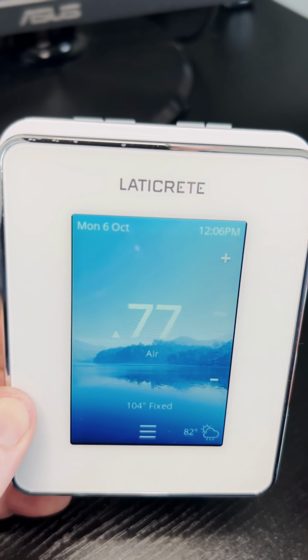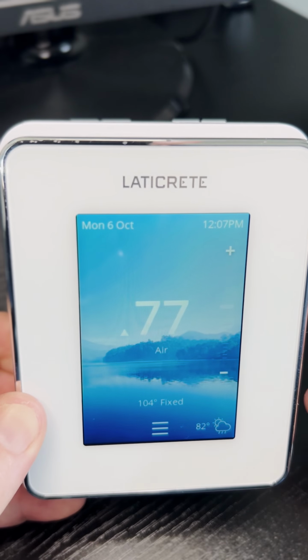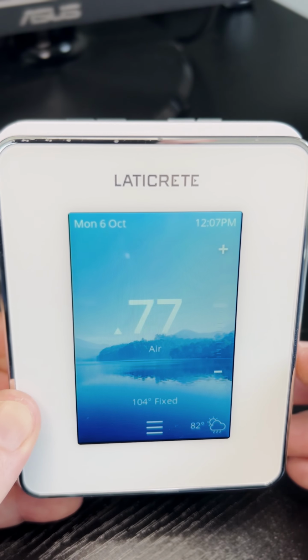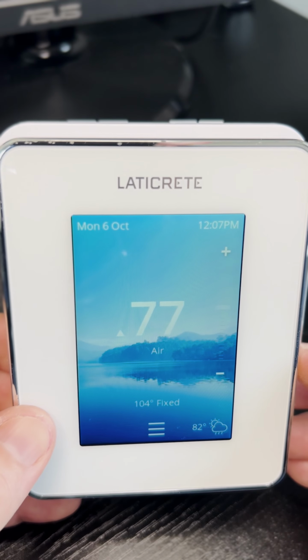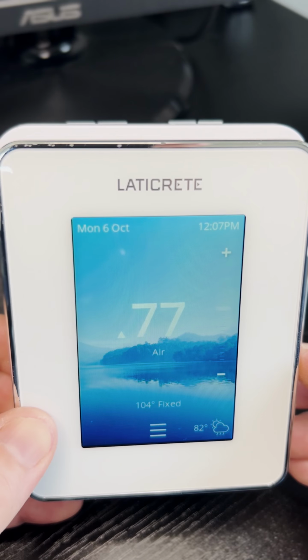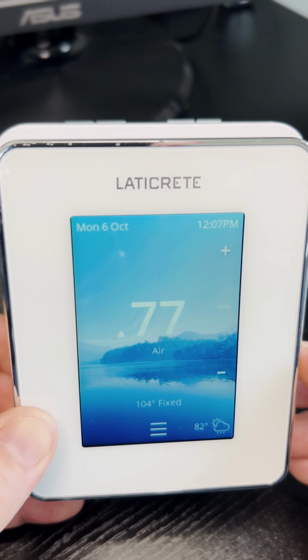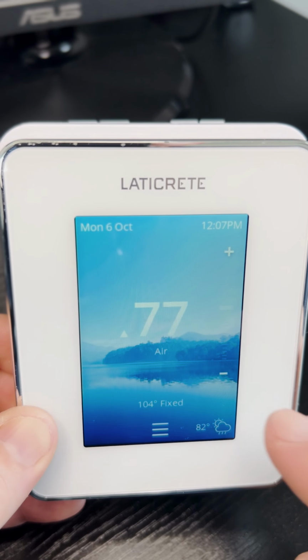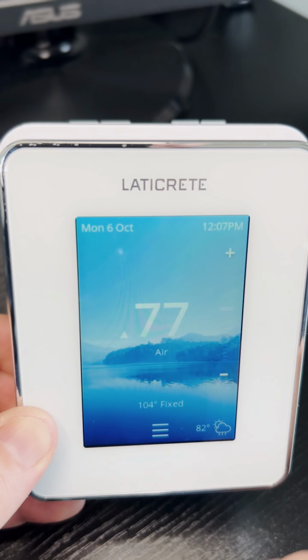That means I'm now using the internal air temp sensor, which means the thermostat is always going to be reading off of the air temp in the room, in which case the floor heat would have to run to the point of actually heating the air in order to see these digits increase.